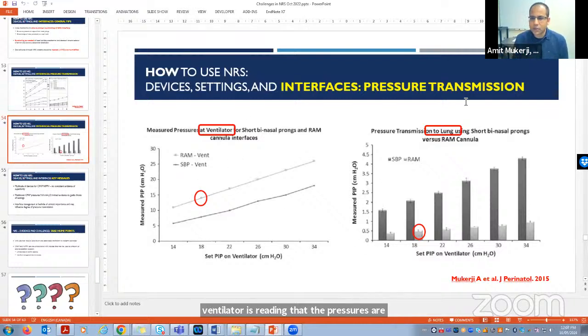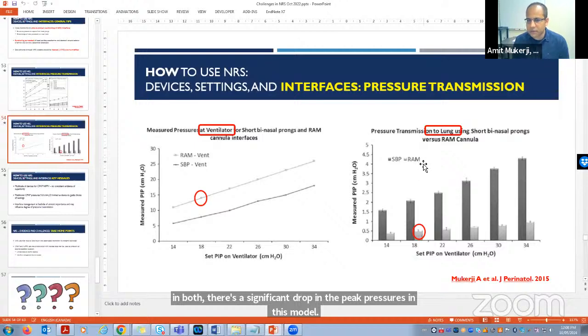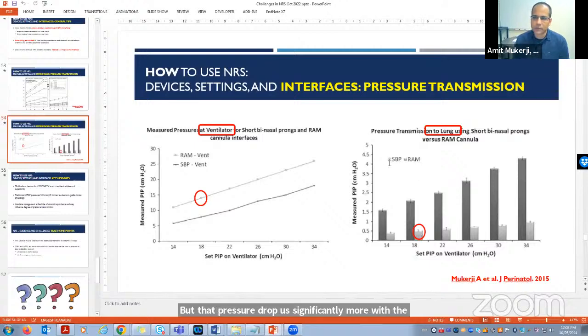These are similar data that I collected during my fellowship, where we looked at this in a lung model. On the right, we are comparing the set PIP on the ventilator and the measured PIP at the level of the lung using a pressure transducer. In both, there's a significant drop in the peak pressures in this model, but the pressure drop was significantly more with the RAM cannula versus a short binasal prong. So it's something we have to keep in mind. If you are a center that's committed to the use of RAM cannula, you have to accept that the pressures you set to achieve the same transmitted pressure will have to be much higher.